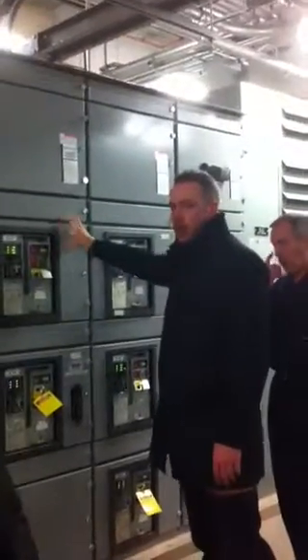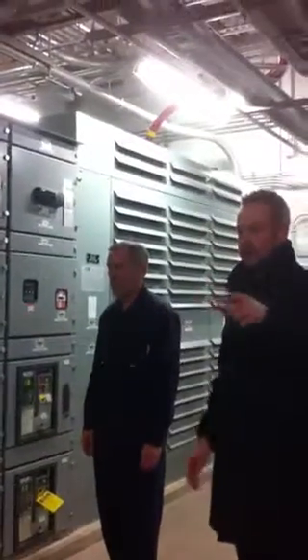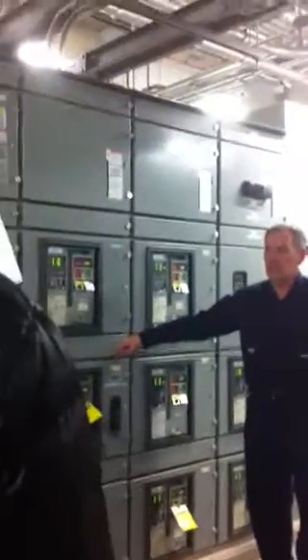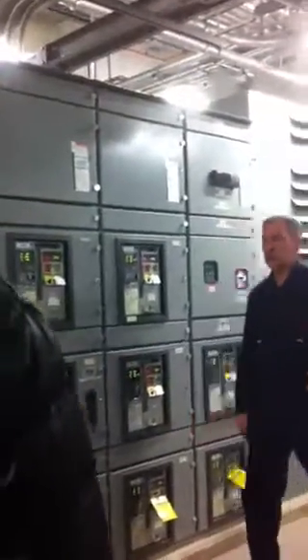Need to take a transformer down. The second transformer that's remaining is capable of supporting both halves of the board. When you look at this, although physically right now it looks like a single board, there is actually two 3,000 amp buses, one on this side, one on that side, and if you look at your single line, they will be two small little lines with a breaker in the middle. That breaker in the middle is called a tie breaker. It remains normally open. So the way that this system operates normally is transformer TX1 feeds board number 1, transformer TX2 feeds board number 2, and they both sub-feed separately.